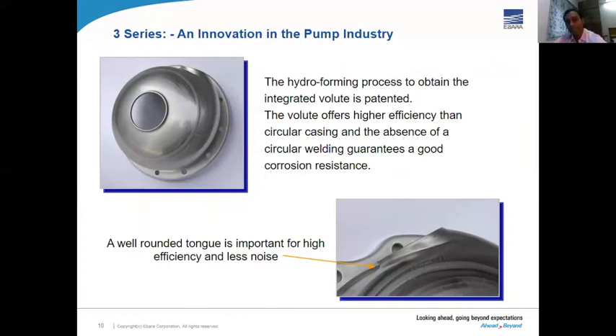The casing is manufactured by a hydroforming process where we inject water at almost 1400 bar, which forms the casing like a balloon. That's how we get a precise volute, which gives high efficiency, and we also have a low NPSH requirement compared to the end suction pump.